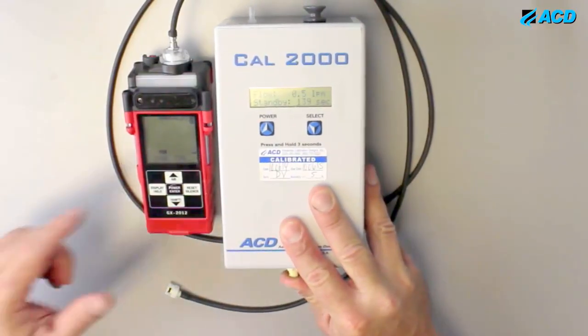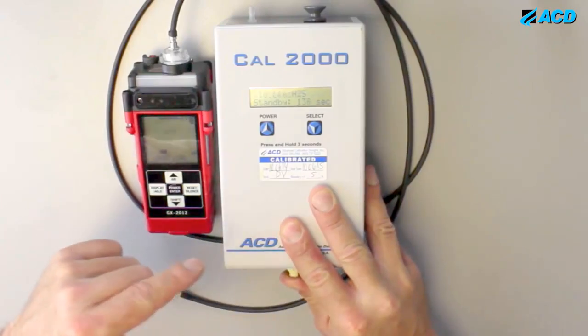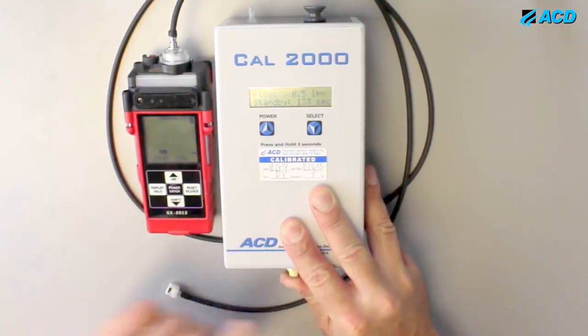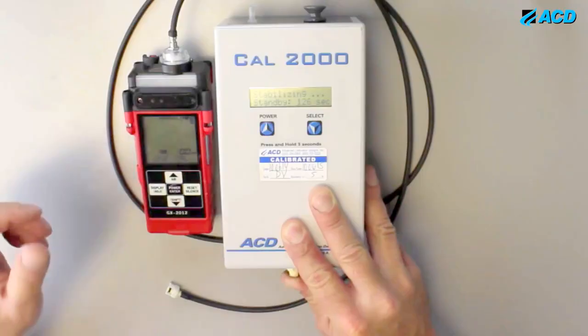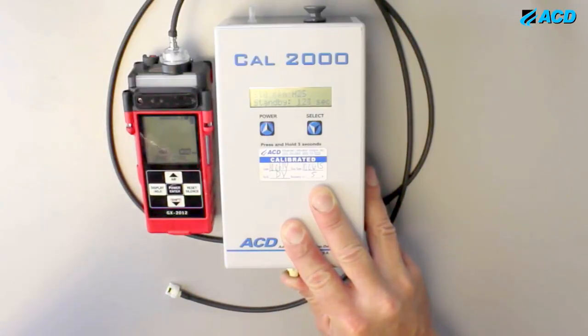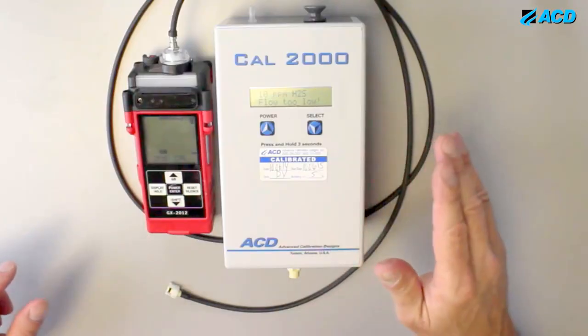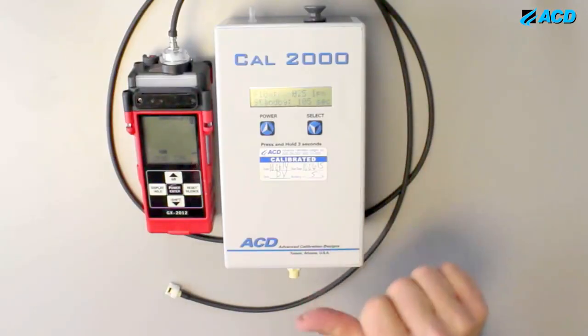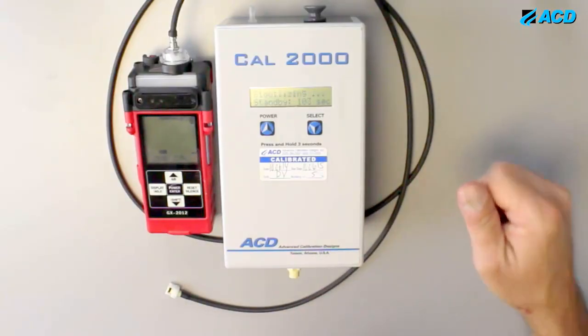If I hooked it up to that unit, I don't know if you can hear it, but the pump is ramping up because I've plugged the outlet. This happens also if you pinch the hose or something. The Cal 2000 has to have the correct flow rate, so it monitors for that. And if the flow rate is not correct, it'll give you a flow failure indication, and then eventually it will shut itself off if you don't cure that situation where you've got kinked hose or so. There's flow too low, right? So it's warning you that if I'd left my thumb over the hole, it would have shut itself off eventually.